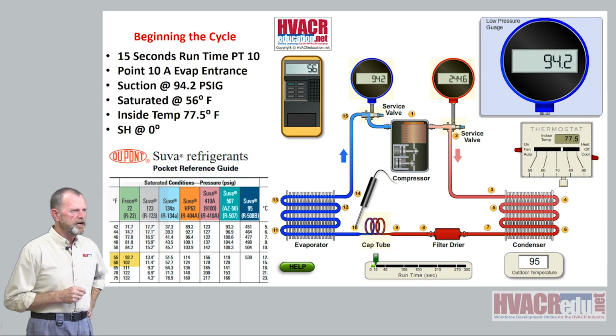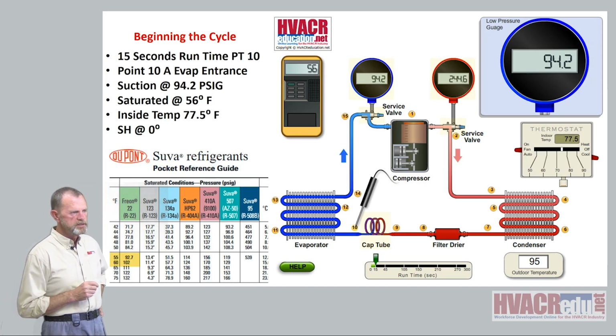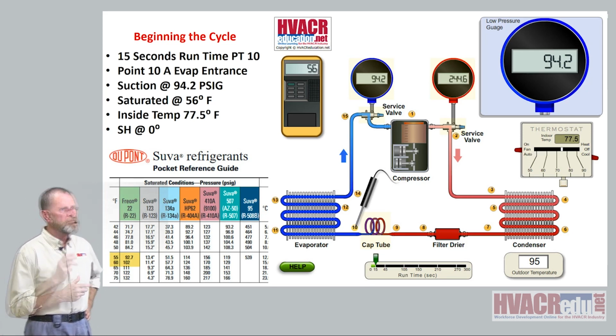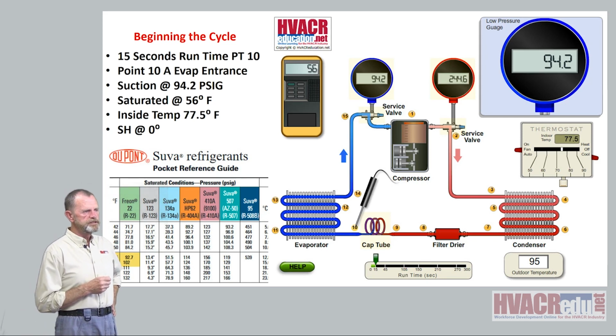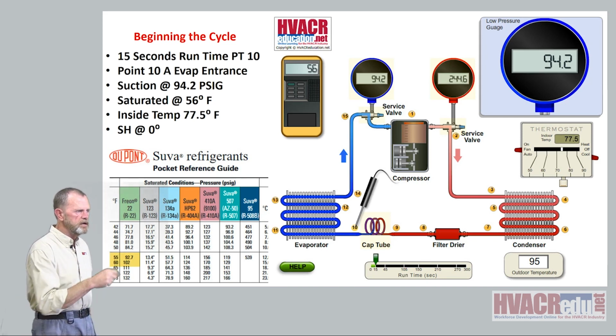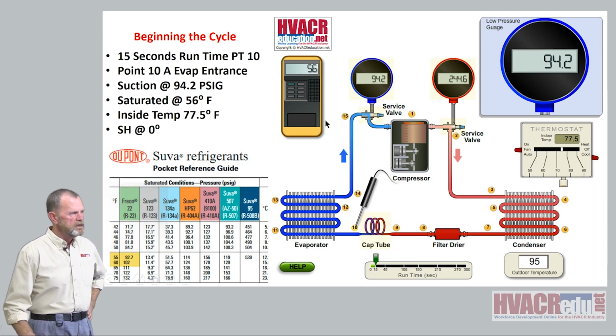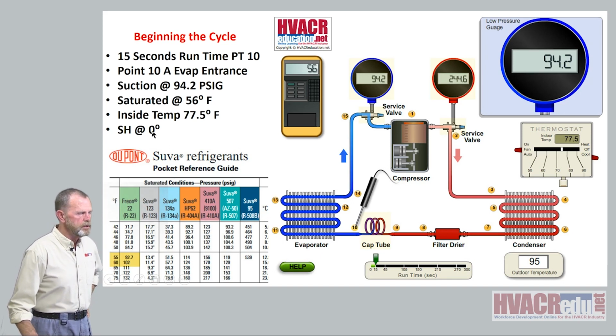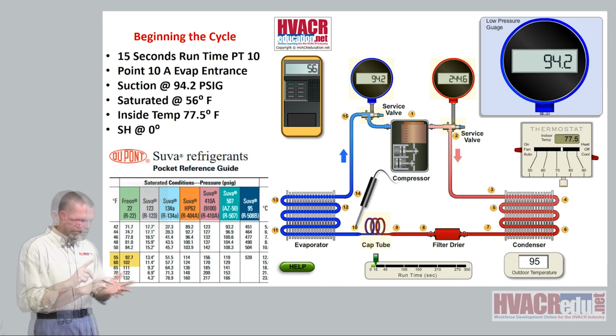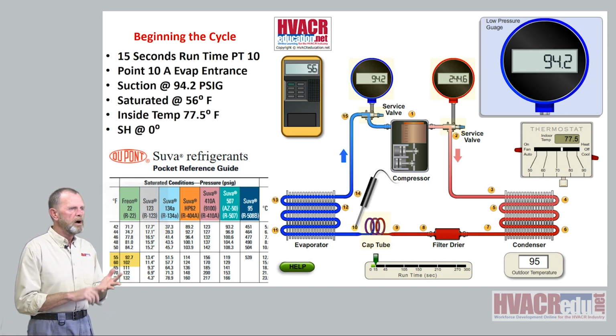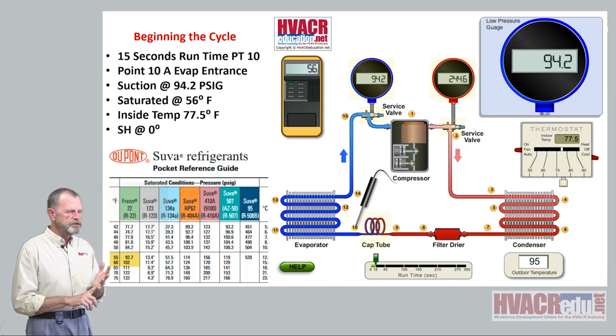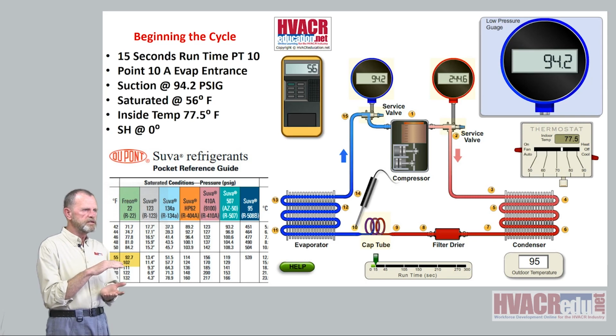If you ever want to check saturated condition, or even better, if you want to check the type of refrigerant that might be in the system, as long as it's not something somebody mixed, you go right to the inlet of the evaporator, you're running the system, you're taking the suction pressure, and you should be able to determine what type of refrigerant's in there, because if there's a saturated condition anywhere, it's going to be at the outlet of the metering device. You can't miss. So what does that mean? I've got 56 on the temperature probe. I've got a saturated condition of 56 off my pressure temperature chart. That means my superheat is 0. Remember, superheat is measured temperature with a surface probe minus the saturated condition, and that tells you how much heat above the saturated condition you have in the vapor.